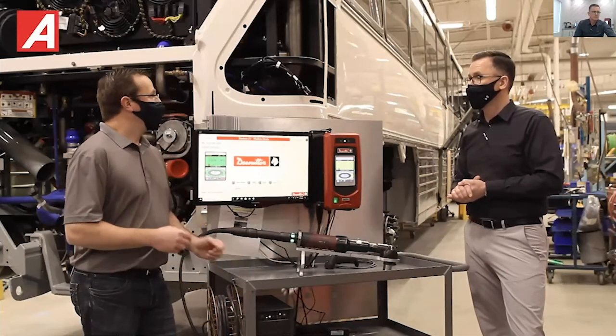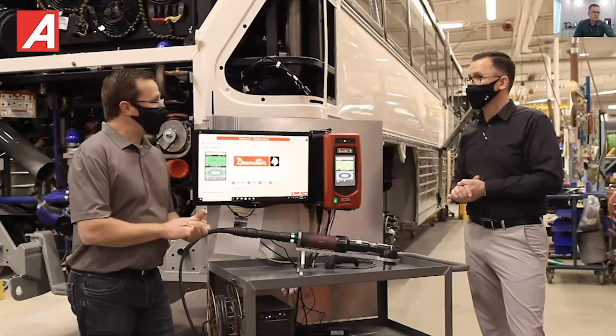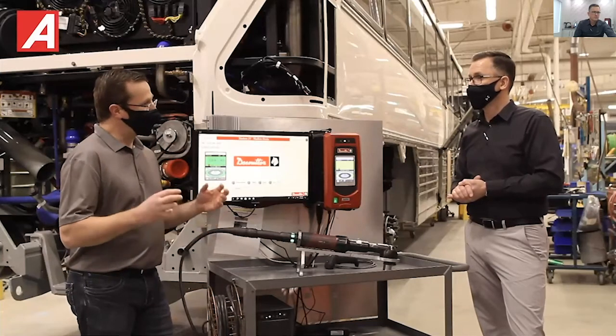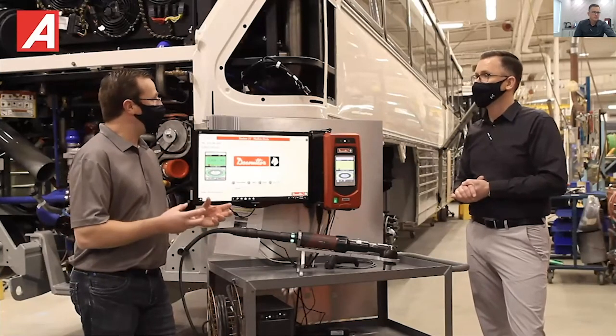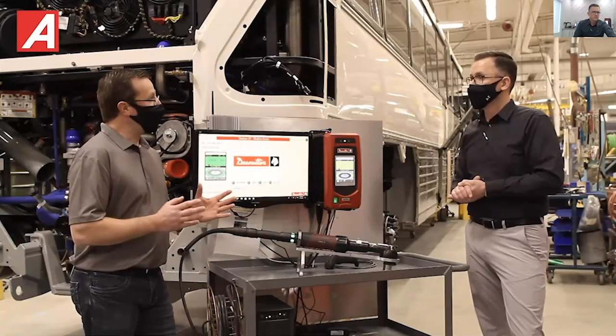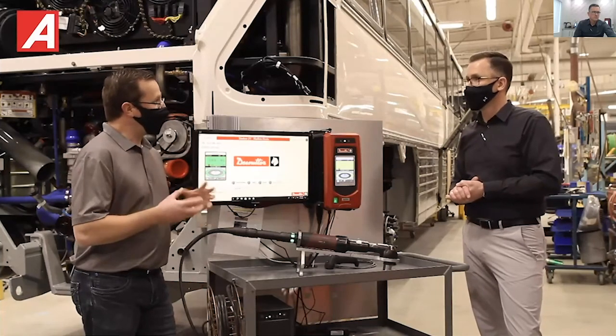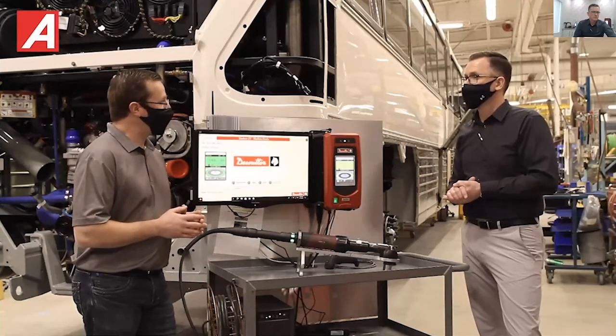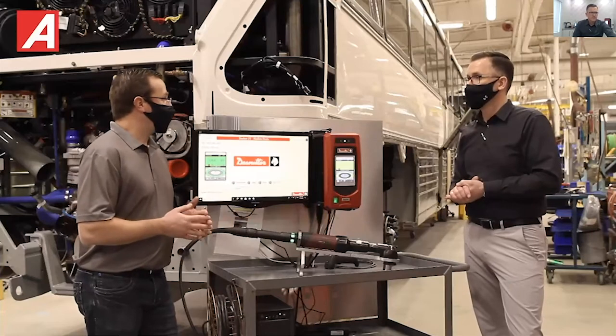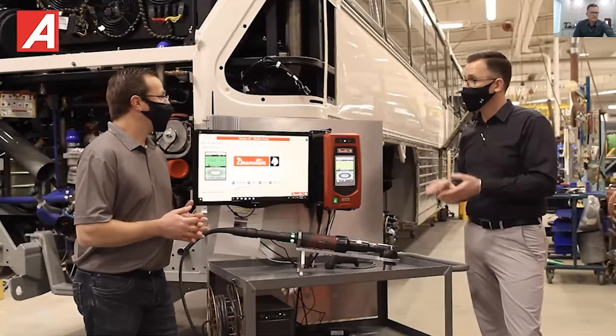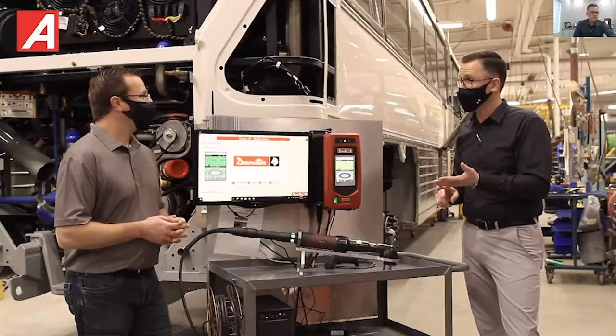Another one would be reusing fasteners. When you reuse a fastener, you actually condition the threads of the nut and the bolt, and your clamp force goes up when the threads are conditioned. It changes the joint completely, and you could be into the yield point of your fastener at that point. So it's very important to have controlled hardware coming into the station.